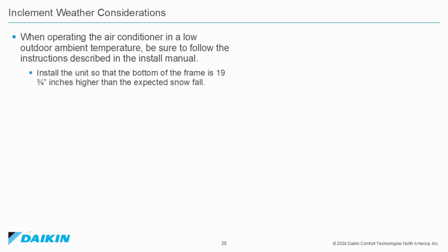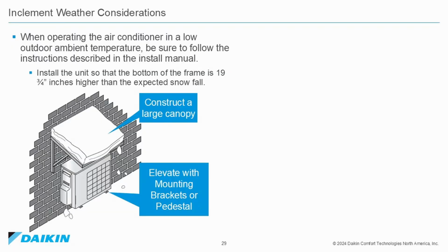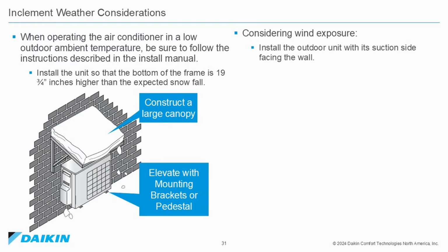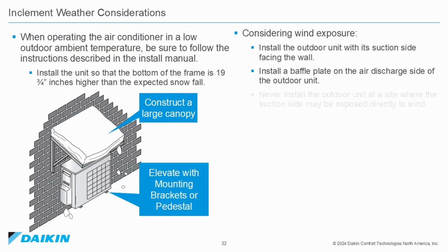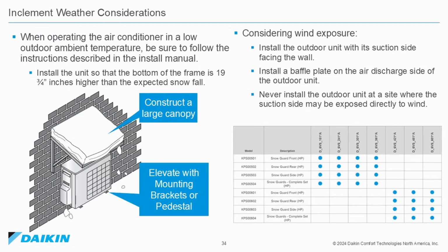Install the unit so that the bottom of the frame is a minimum of 19 3/4 inches higher than the expected snowfall. If possible, construct a canopy over the top and elevate the units by using a wall mounting bracket or pedestal. Consider wind exposure. Install the outdoor unit with its inlet side facing the wall. Install a wind baffle plate on the air discharge side of the outdoor unit. Never install the unit at a site where the inlet side may be exposed directly to the wind. Below, see the chart showing the available options for snow guards.